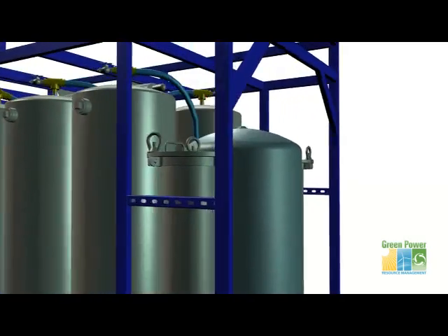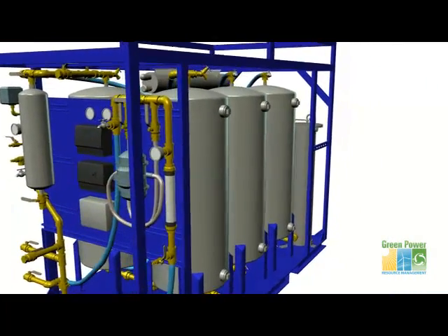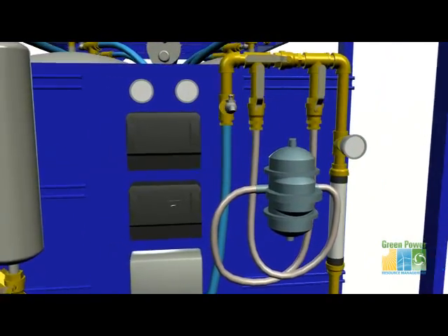Finally, the water goes through a disinfecting treatment. Options of UV light and chemical disinfection are available for this stage of filtration. As an additional measure for stored water, a water-driven chlorine chemilizer pump can be activated and connected to injection valves located on the intake and output pipelines.